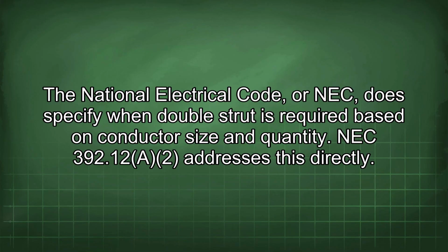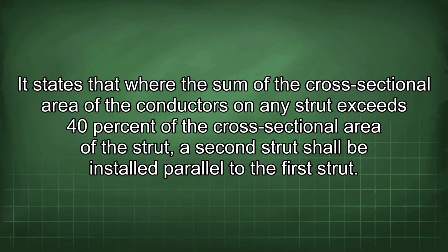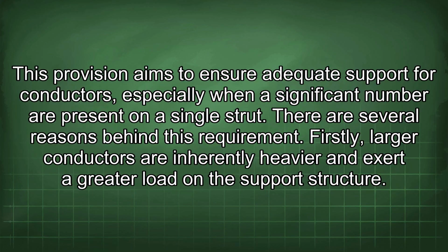The National Electrical Code, or NEC, does specify when double strut is required based on conductor size and quantity. NEC 392.12(A)(2) addresses this directly. It states that where the sum of the cross-sectional area of the conductors on any strut exceeds 40% of the cross-sectional area of the strut, a second strut shall be installed parallel to the first strut. This provision aims to ensure adequate support for conductors, especially when a significant number are present on a single strut.